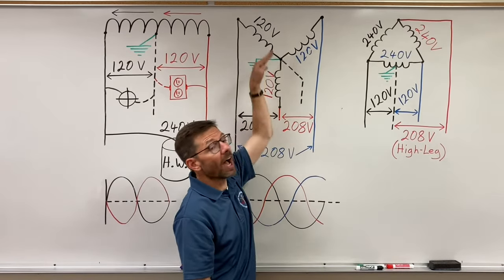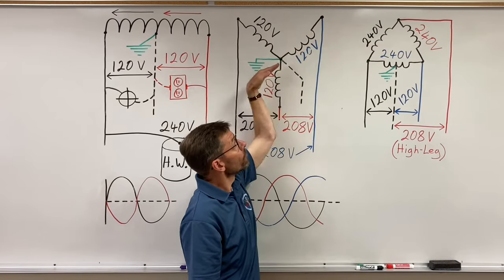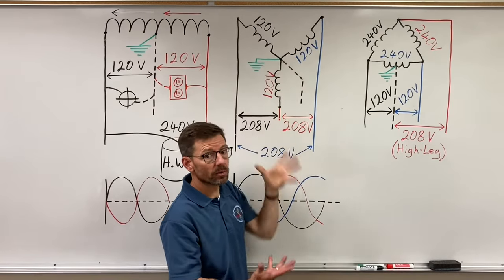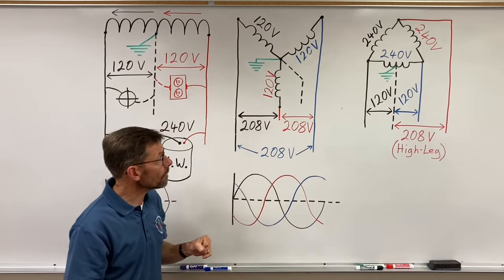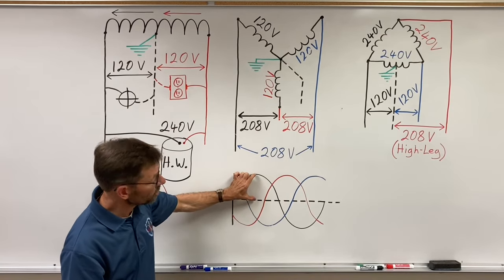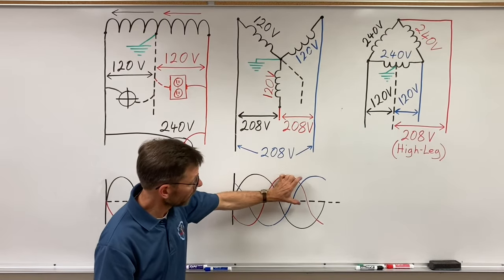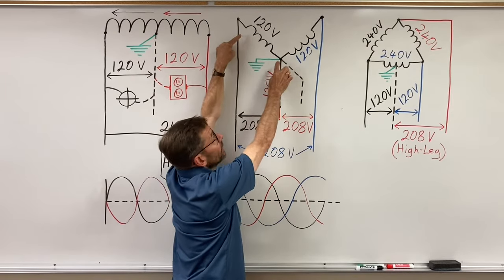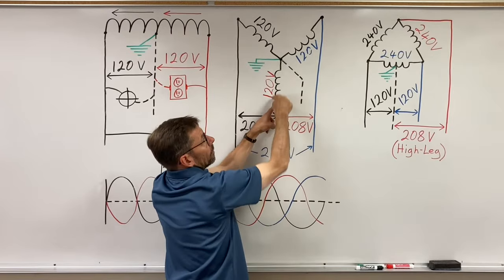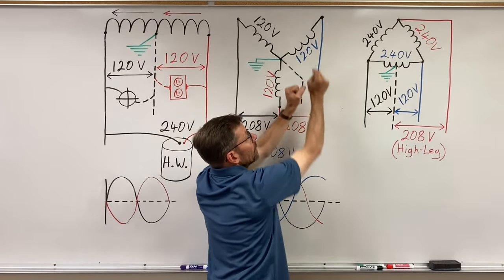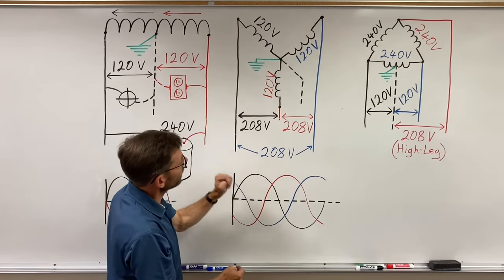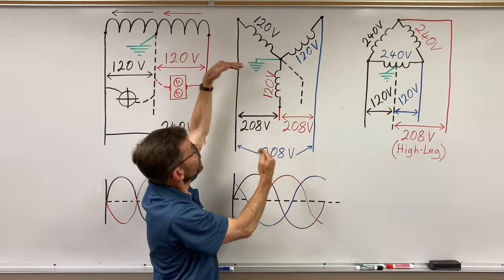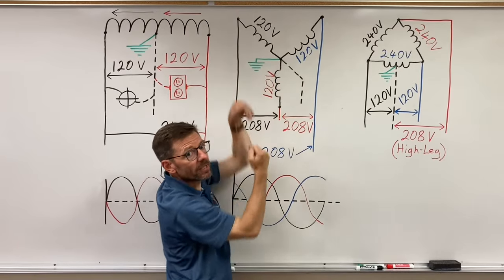Therefore, the lines in the Y or star configuration have resultant vectors pointing 120 degrees apart from each other. Although black to neutral is 120, red to neutral is 120, and blue to neutral is 120 — just across each individual winding — when I go black to red, I go through two windings. But it's different from the split-phase system because those windings are 120 degrees out of phase from each other. If they peaked and troughed directly opposite, I could just add them.